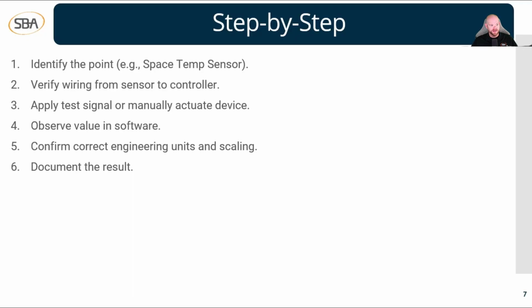So once we've done that, the next thing we can do is apply a test signal or manually actuate the device. So this is talking two things here. So we can apply a test signal. So this would be like a given resistance reading for this space temperature sensor. And then we can take a resistance temperature chart, and we can verify to make sure that we're getting the right resistance reading. And then the second point on this here is to manually actuate any device. This could be like a valve actuator or a damper actuator, something like that.